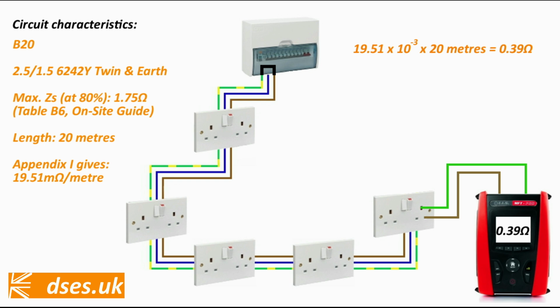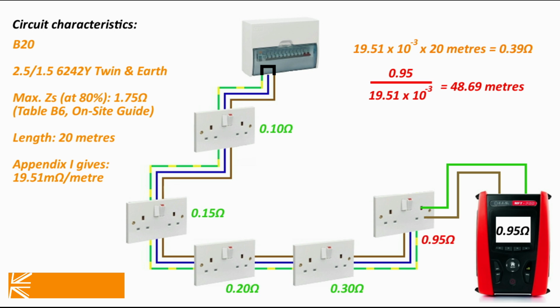Marvellous! However, the electricians who installed the circuits on my house are probably all dead by now, and I doubt if they were still around they'd recall the length and route of the wiring, so we're not going to know the precise length of any given circuit in order to be able to confirm our readings are correct in most properties. Let's assume then that at what we believe to be the circuit endpoint, we don't get 0.39 ohm, we get 0.95 ohm. The maths says that corresponds to a circuit length of over 48 meters, so alarm bells are ringing if you're in a small abode, especially if previous accessories were checking out with numbers that better met expectations, as that suggests a loose connection, and loose connections are exactly what's supposed to upset an AFDD.